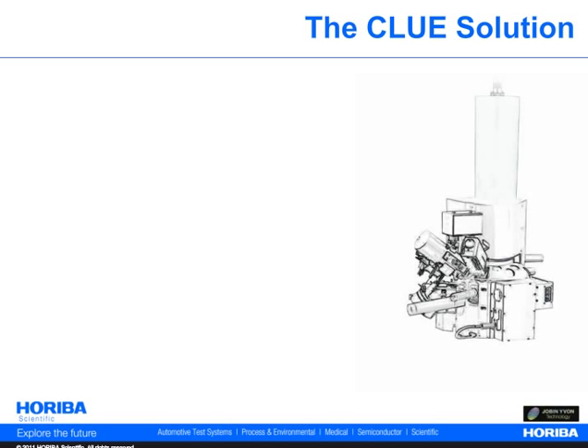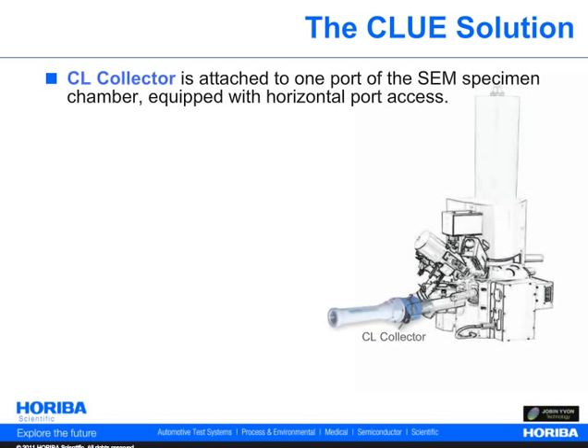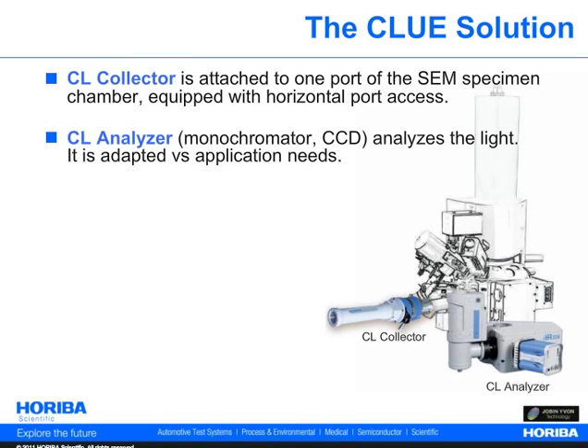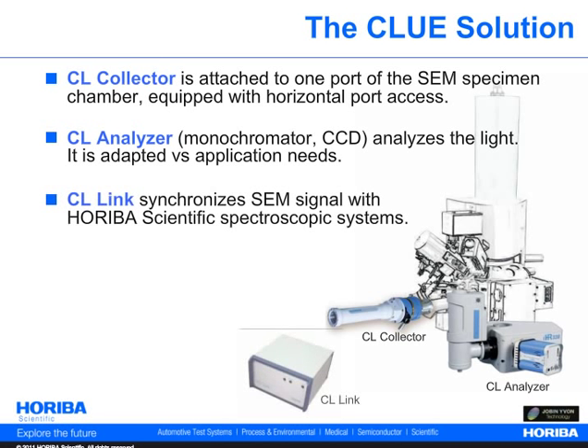Main components of the CLUE include a CL collector, which is attached to an SEM chamber equipped with a horizontal port access. The CL analyzer analyzes the light and is adapted to your experimental requirements. HORIBA Scientific has extensive experience in spectroscopic systems and the design of the CLUE is best adapted to fit your application needs. The CL-link is the electronic controller allowing perfect synchronization between the SEM and HORIBA Scientific spectroscopic systems for mapping and image processing.